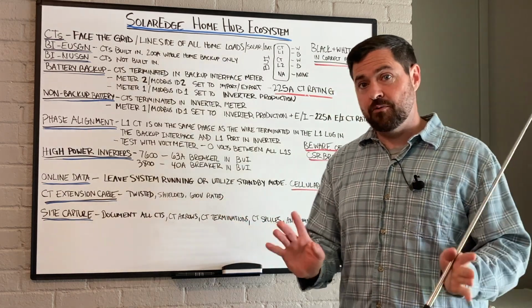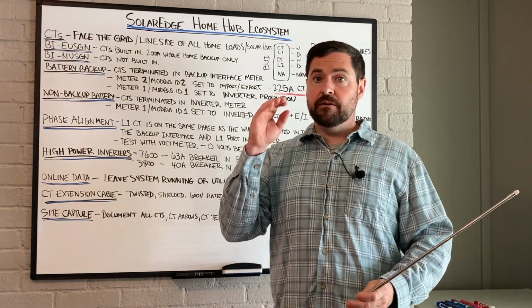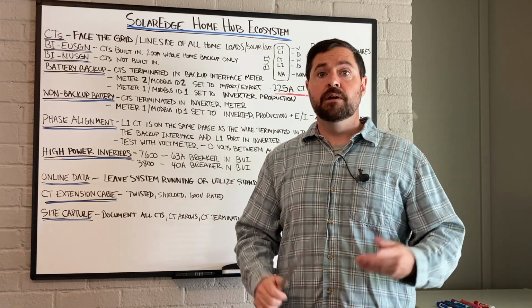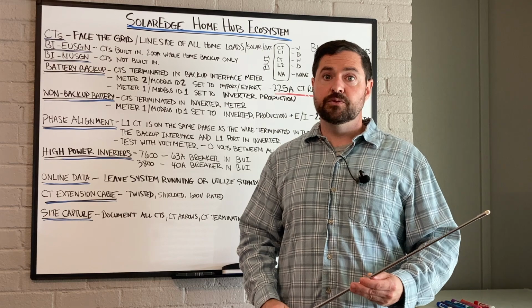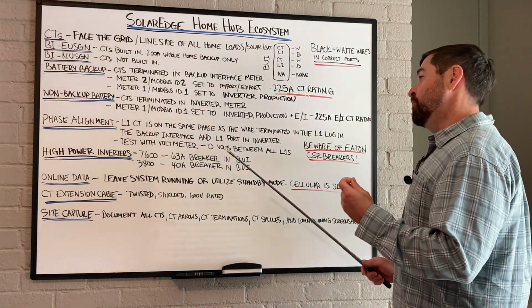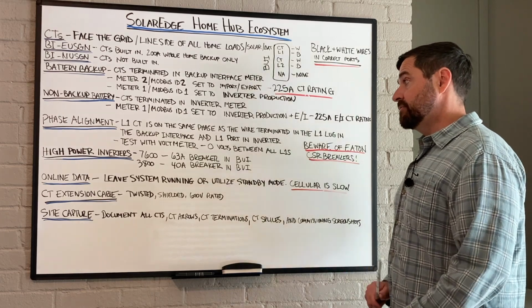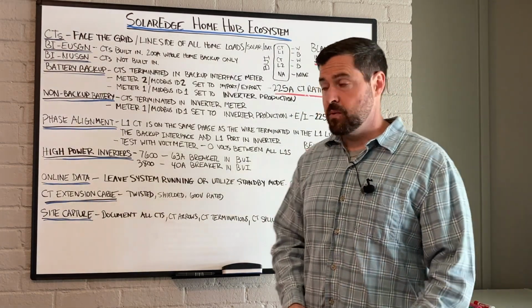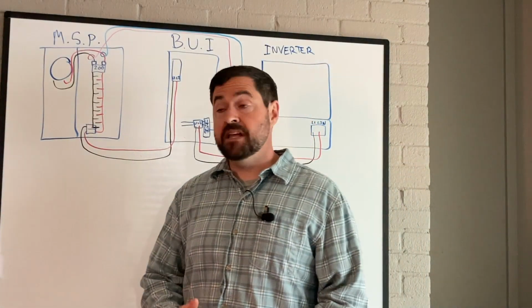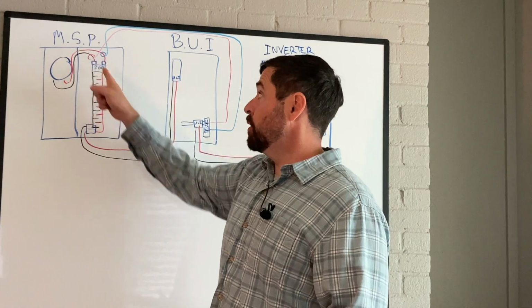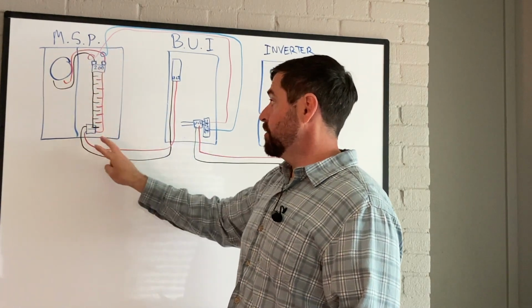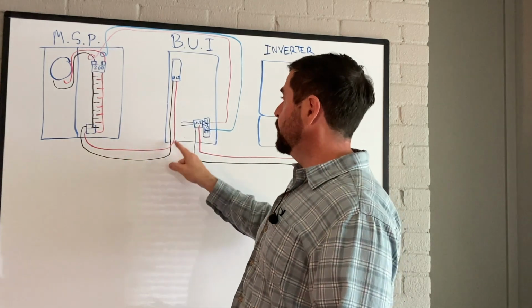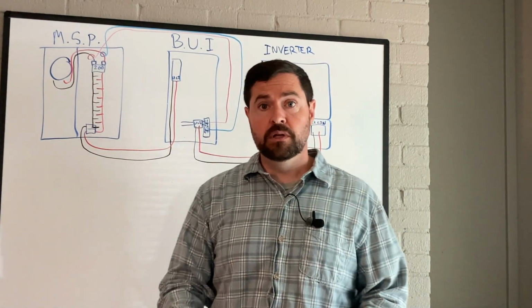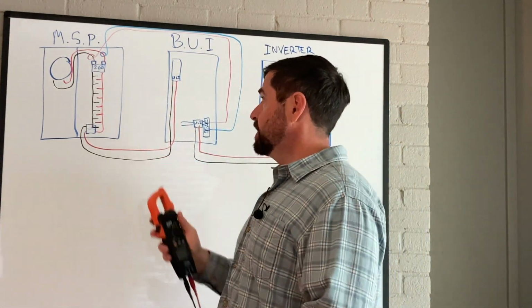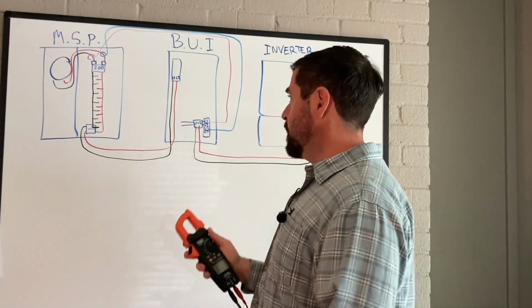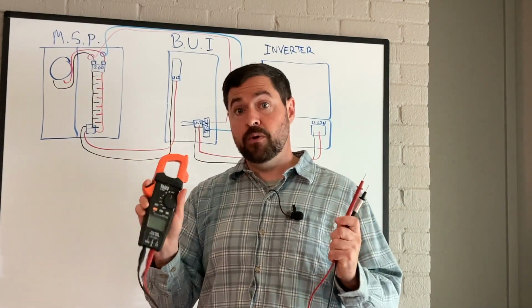Do not waste your time running black wires. Keep track of your L1 and your L2 all the way through the system. Carefully make sure you don't cross L1 and L2 anywhere. And then test with a voltmeter at the end of every installation to make sure you didn't go wrong somewhere. Again, to test phase alignment, we're going to want to make sure we keep the L1 and the L2s consistent through the entire system, that at no point do we cross L1 and L2. So not only can you do that by carefully color coding the wires and tracing them all the way, once you're done, you can verify with a voltmeter.